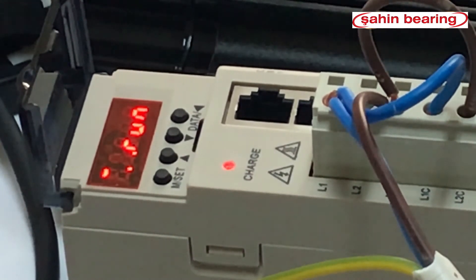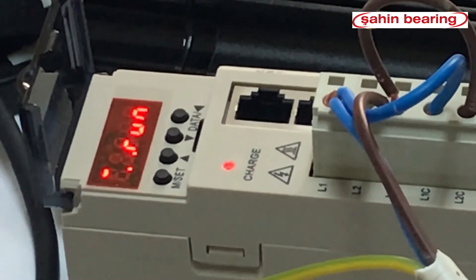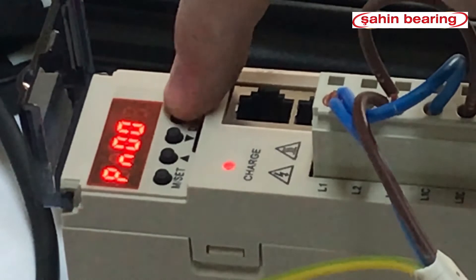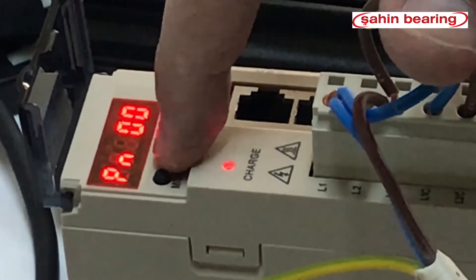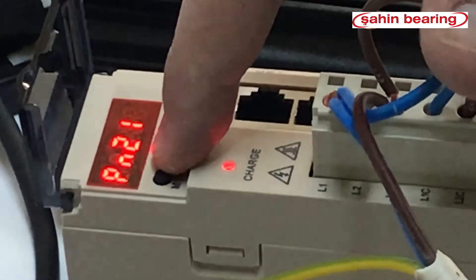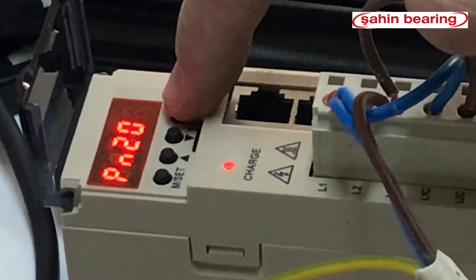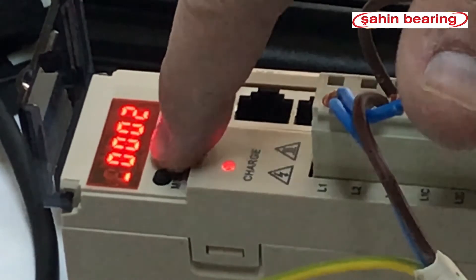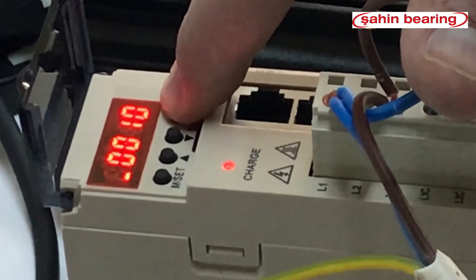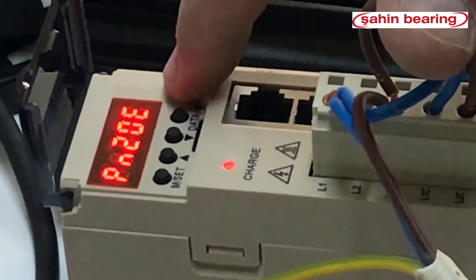By setting the divisor parameter to 10, we will reduce 10,000 pulses to 1,000 pulses. By pressing the MSET key twice, we go to the parameter section and type 20E with the data and up-arrow keys. With the data key we enter into it and set our coefficient to 10. 10,000 divided by 10 equals 1,000.